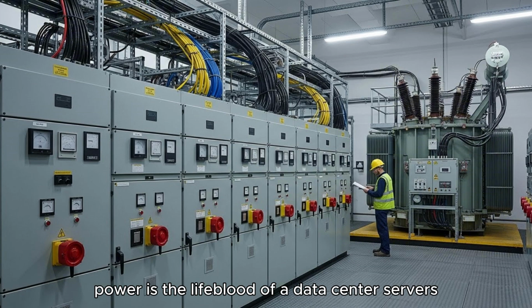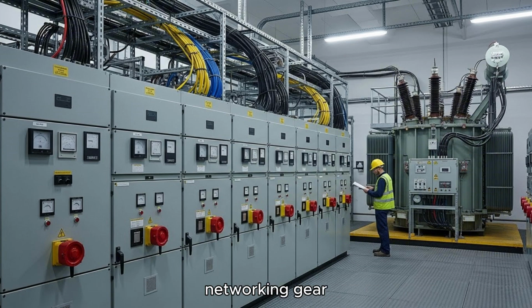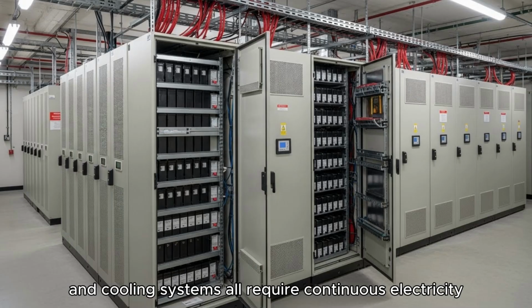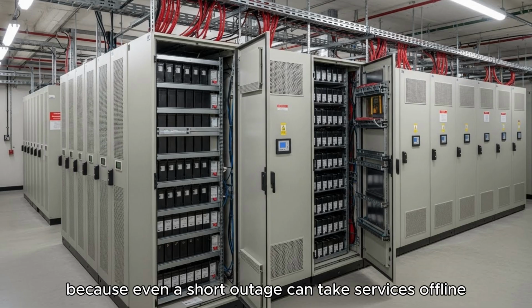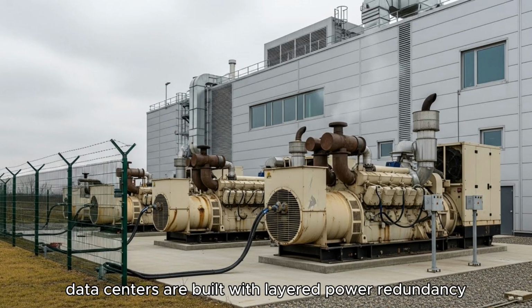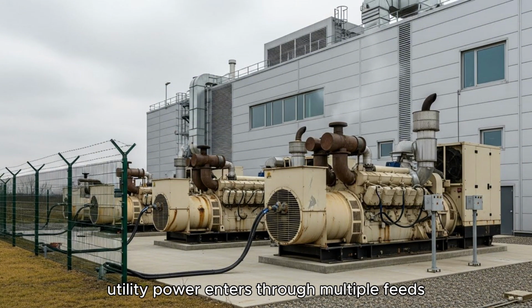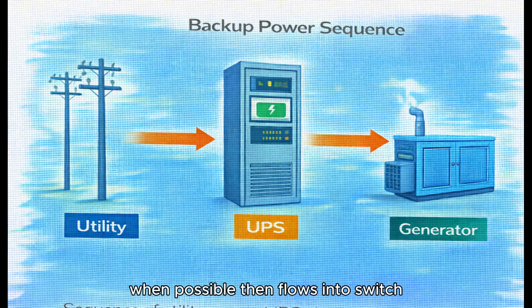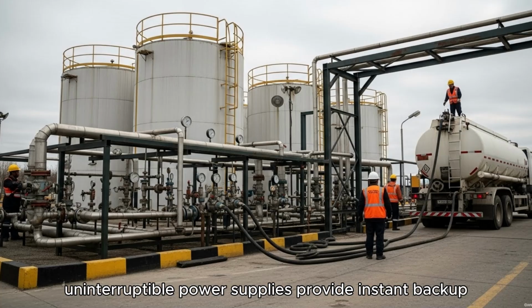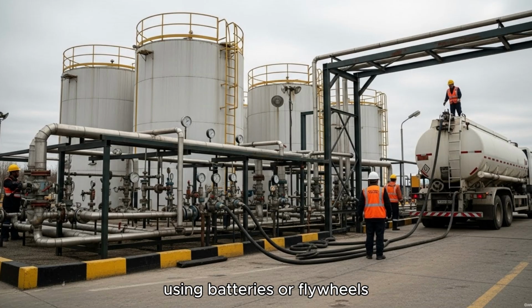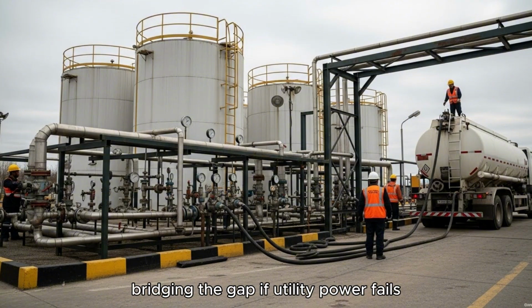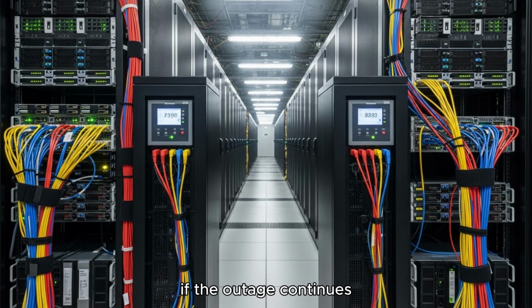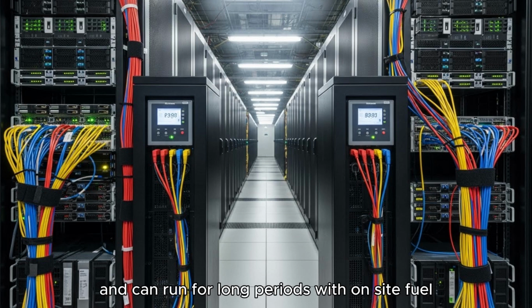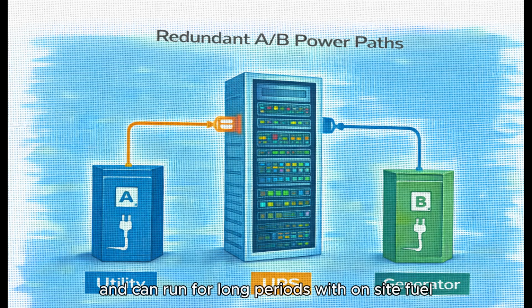Power is the lifeblood of a data center. Servers, networking gear, and cooling systems all require continuous electricity. Because even a short outage can take services offline, data centers are built with layered power redundancy. Utility power enters through multiple feeds when possible, then flows into switchgear and power distribution units. Uninterruptible power supplies provide instant backup using batteries or flywheels, bridging the gap if utility power fails. If the outage continues, diesel generators start within seconds and can run for long periods with on-site fuel.